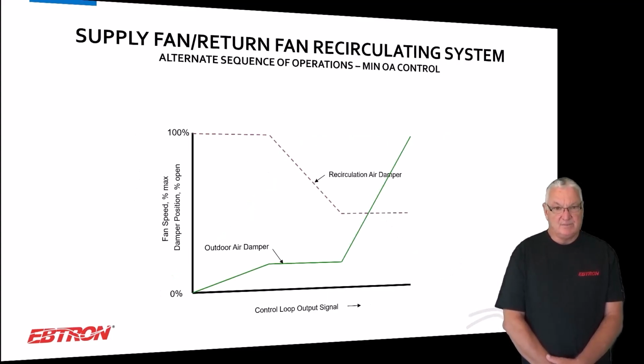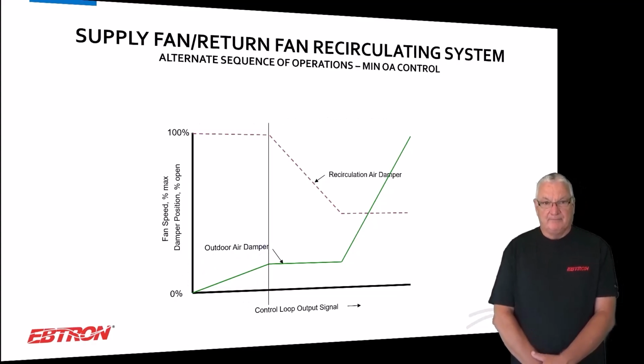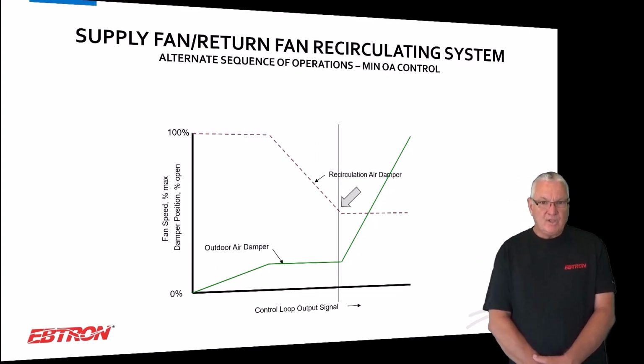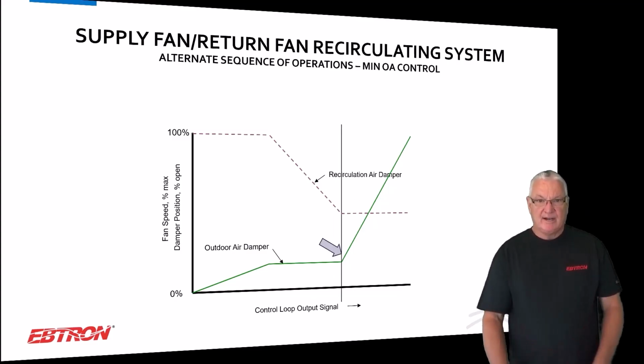The alternate is pretty much what we already talked about. You're doing it with the recirc air damper instead of the outside air damper. So at any rate, it's pretty straightforward on what we would do there.